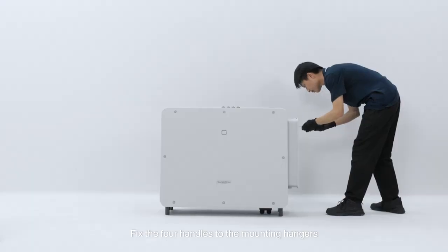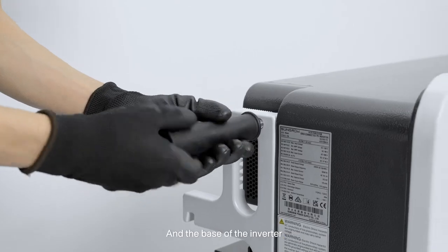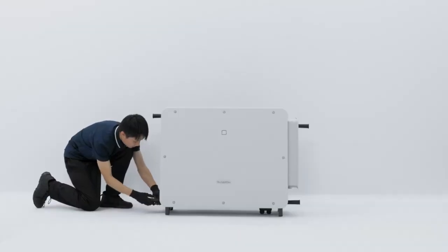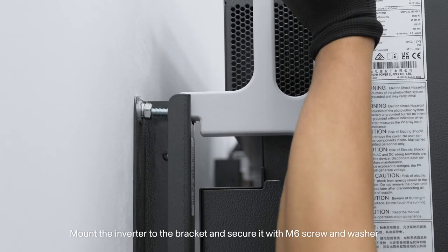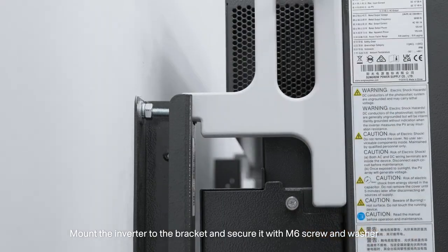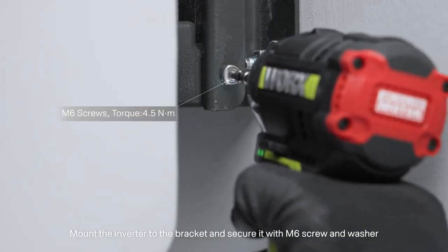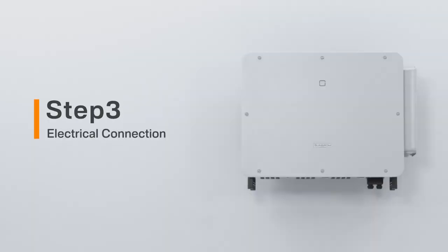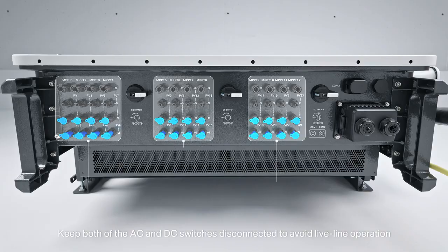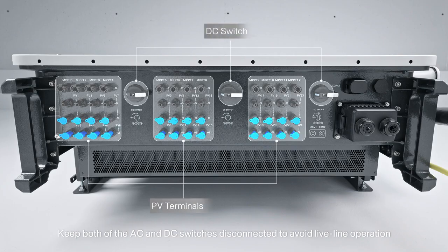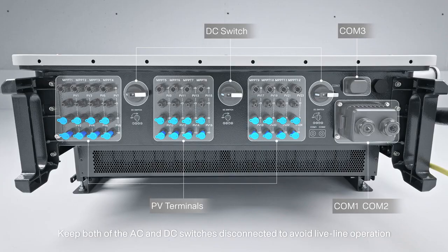Fix the 4 handles to the mounting hangers and the base of the inverter. Mount the inverter to the bracket and secure it with M6 screw and washer. Step 3. Electrical connection. Keep both of the AC and DC switches disconnected to avoid live line operation.